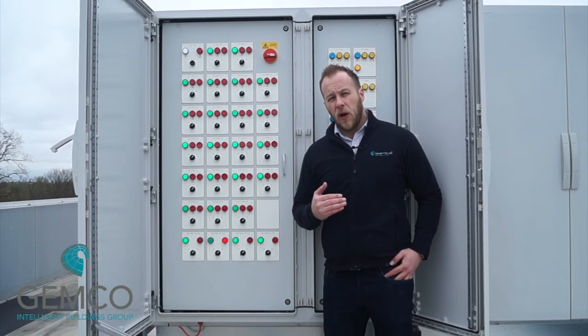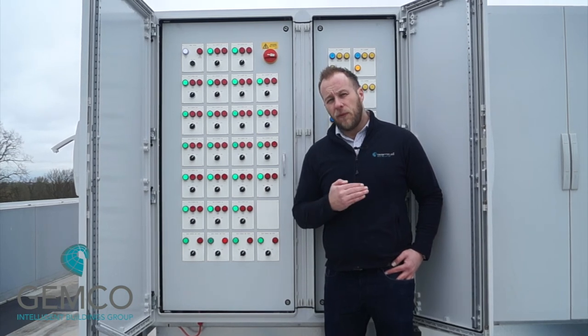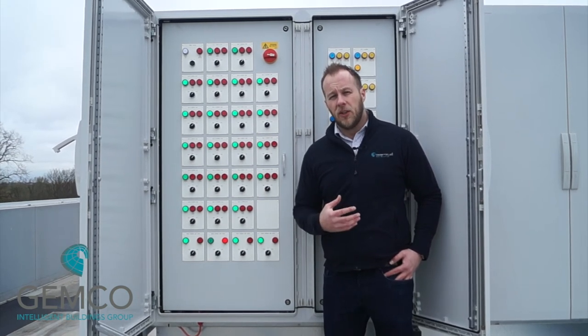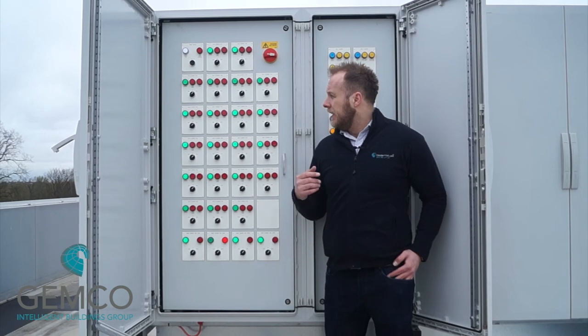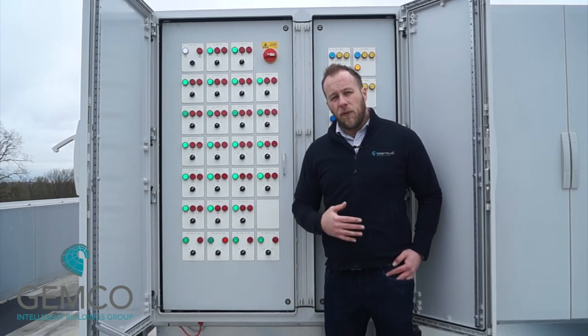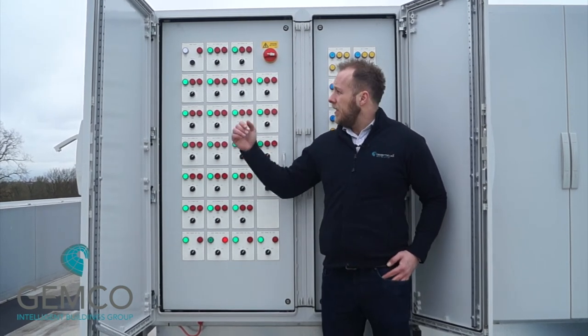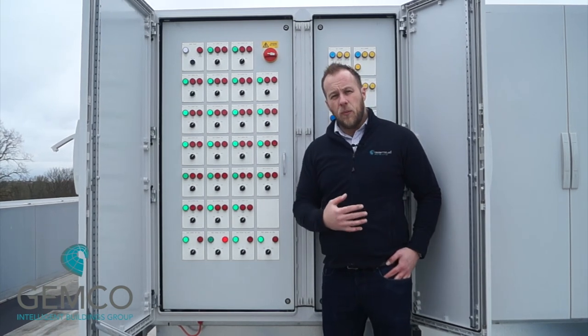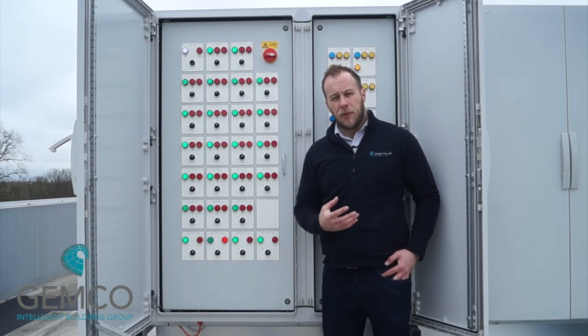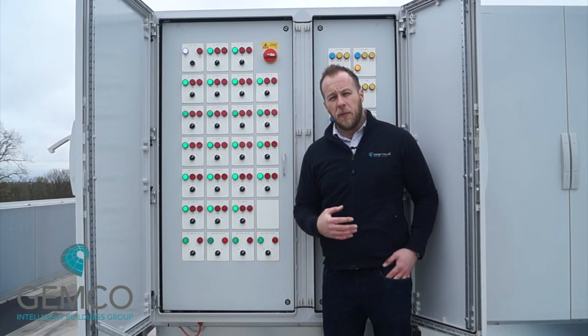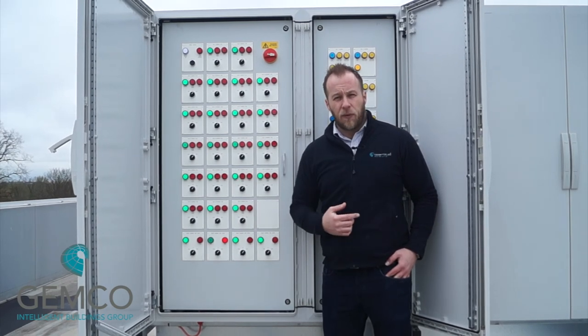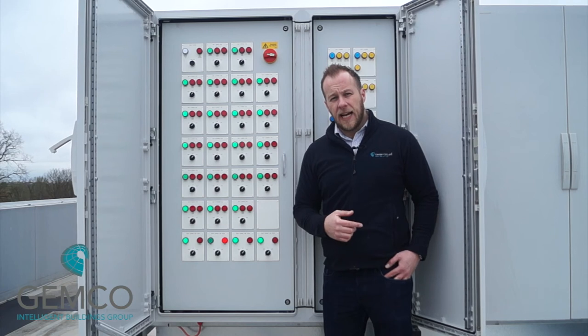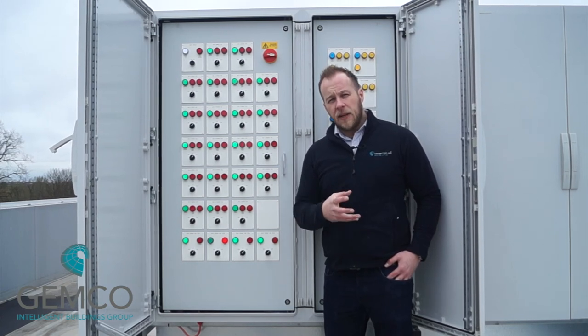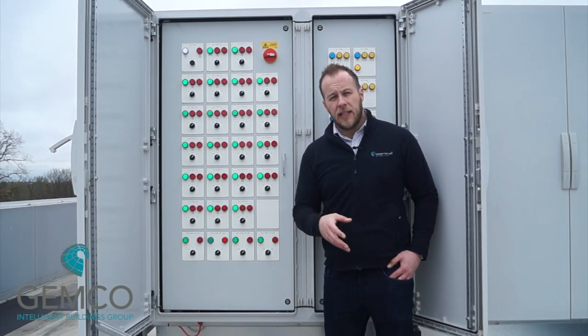But if the flow isn't established and detected, then we'll fail the fan and an alarm will be raised on the BMS. Okay, once the fan is healthy and it begins to run, then we start to temper the air. So the temperature from the CT circuit fed from the boilers will serve each three-port valve on each air handling unit, and the heat will be there ready to use should the air handling unit need it.